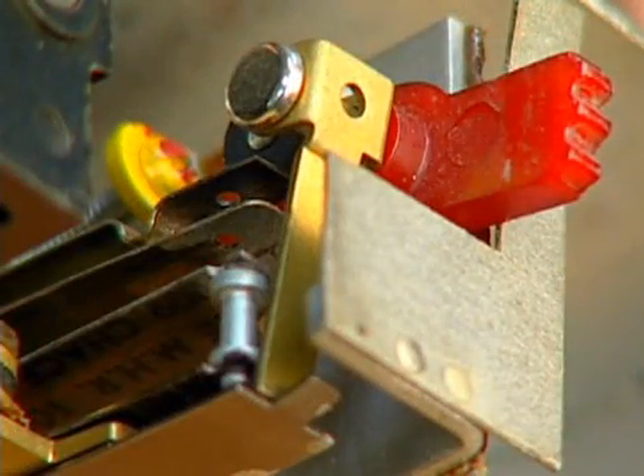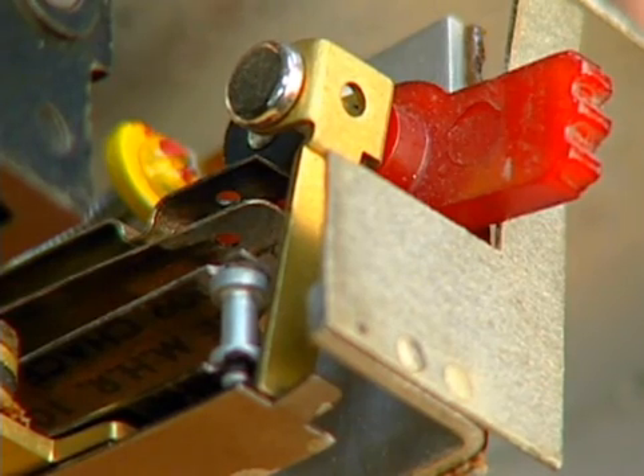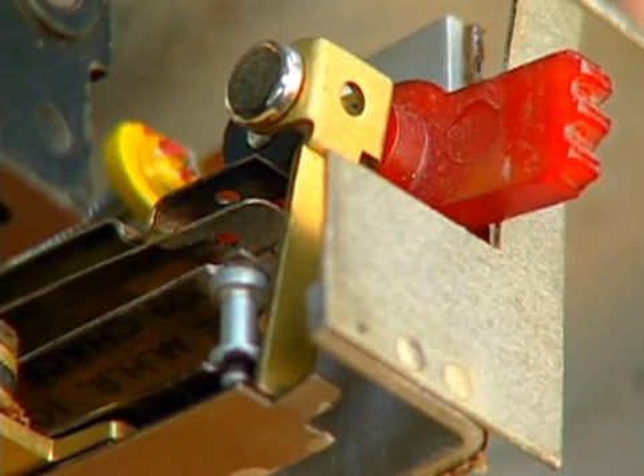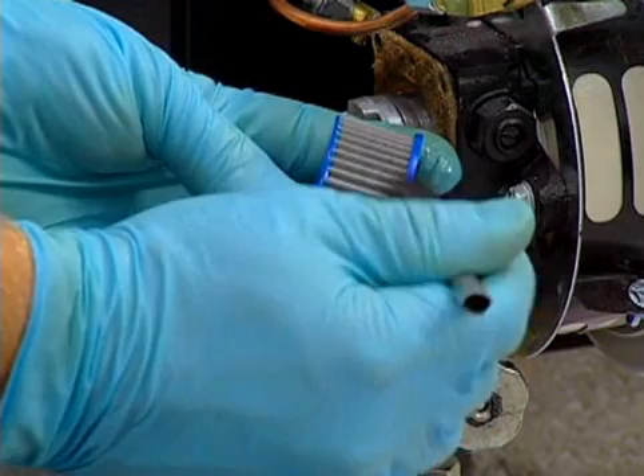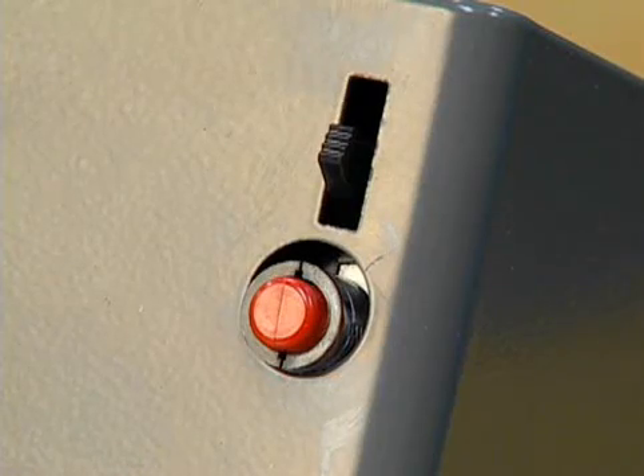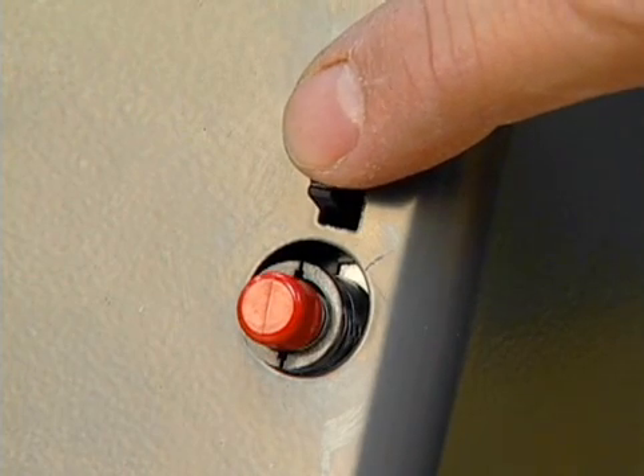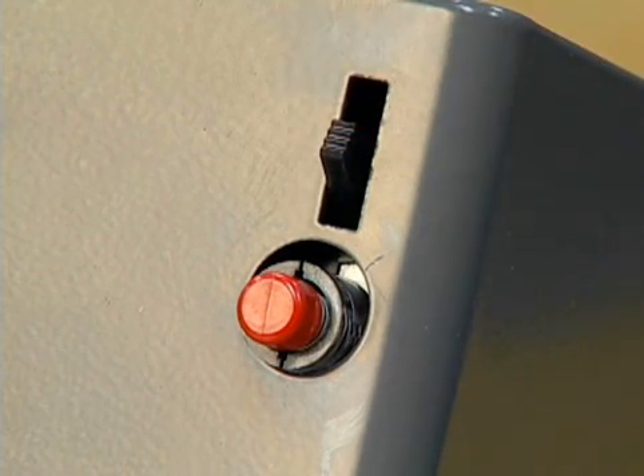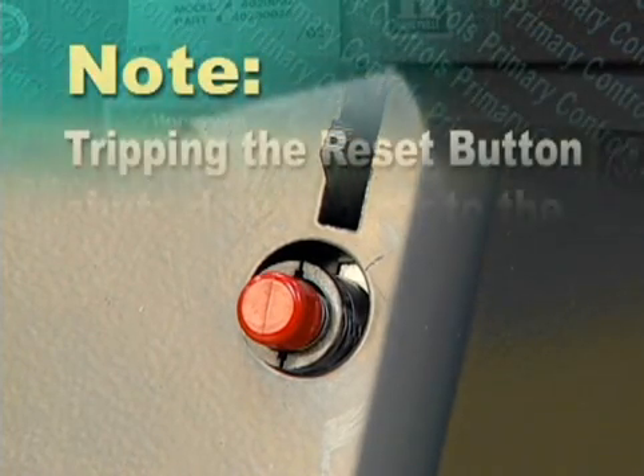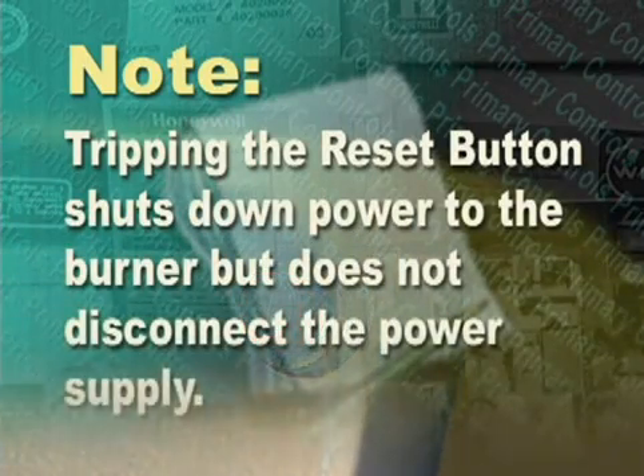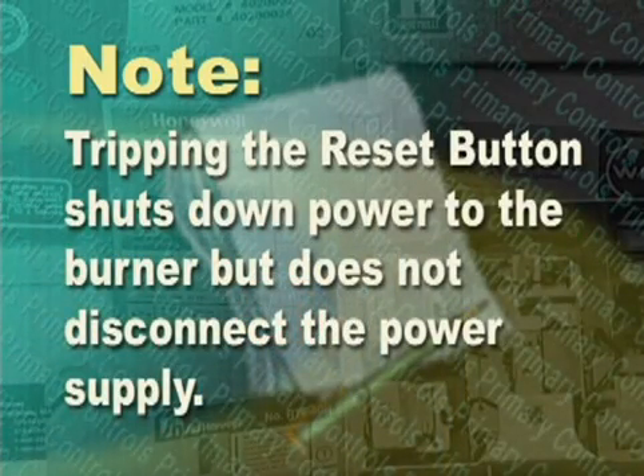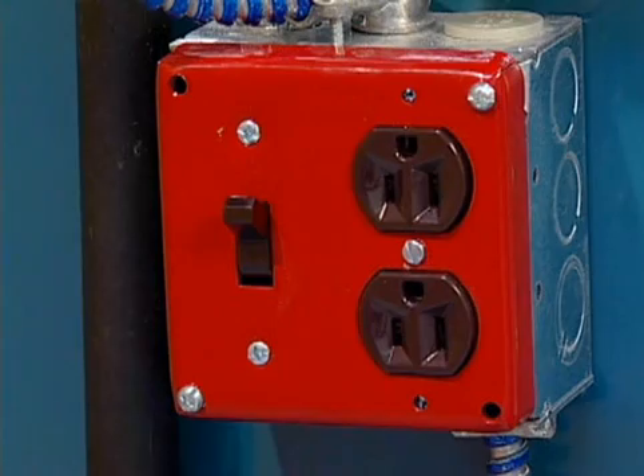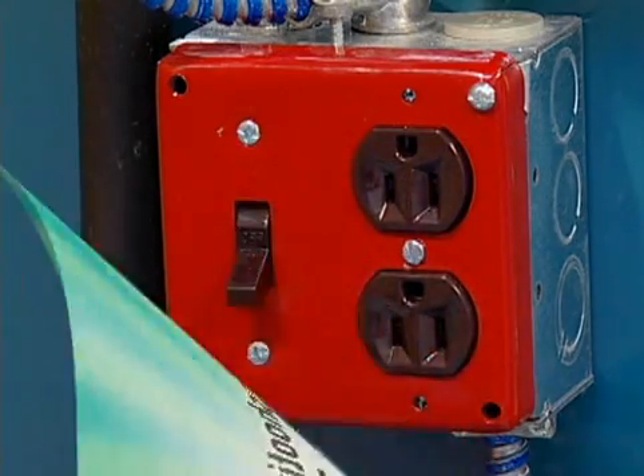Some service technicians make it a habit to put these stack switches off on safety as an extra precaution to keep the unit from starting while they're performing maintenance on the oil burner. Some models have a push lever to do this manually. Simply push the trip lever and the reset button pops out. Note that tripping the reset button shuts down power to the burner but does not disconnect the power supply. To avoid electrical shock, turn off the electrical supply.